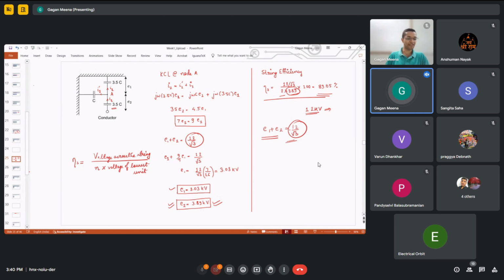We always want a standard. So that is why we said that one unit is roughly 11 kV. That's a standard that we have considered. We have to make all the units with the same voltage, so that has to be the highest voltage. Because if we make it with the lowest voltage, then the insulator which has a higher voltage than that will have the problem of failure. So in this example, the lowest unit has the highest voltage.